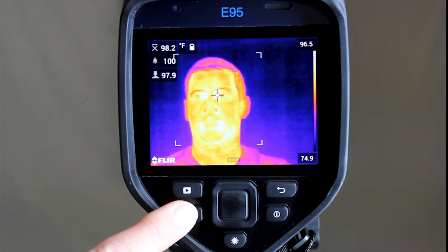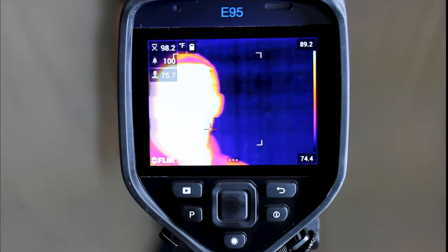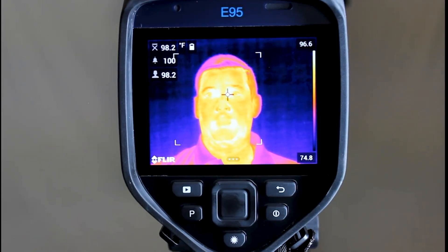When you have everything set, you can start moving subjects to the designated screening location one at a time. Make sure that each subject is screened at the same distance. They should be positioned in the predetermined location that has been marked on the ground. Have them pause for one or two seconds to allow the camera to focus in on the hottest spot, which should be the corner of the eye near the tear duct area. This location provides the closest temperature correlation to human core temperature.